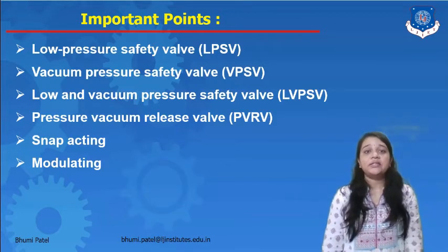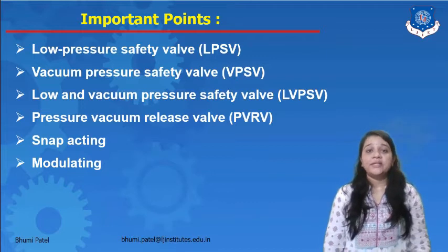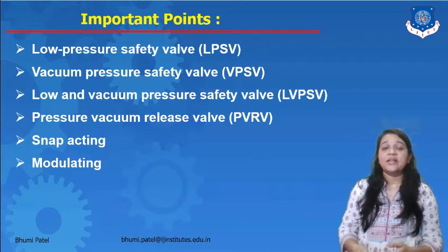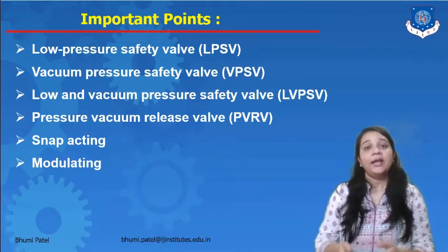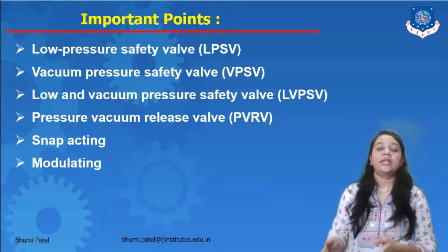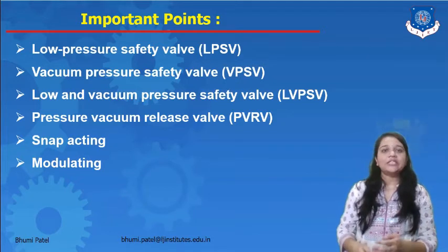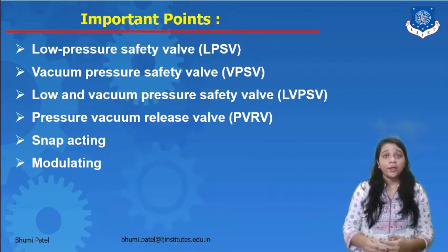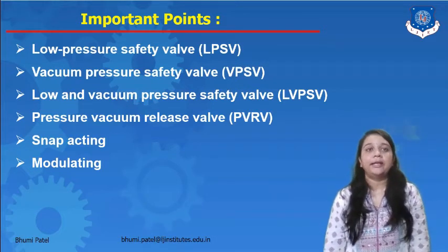And the last one is modulating. It opens in proportion to the overpressure. So whatever pressure is generated in the valve, the outlet opens in proportion to it. That is called modulating of the system. There are some important points related to the relief valve.